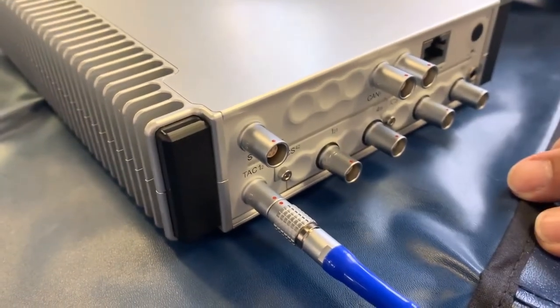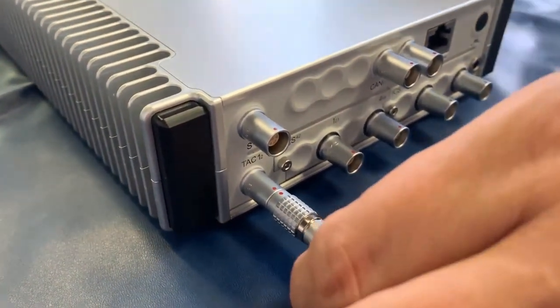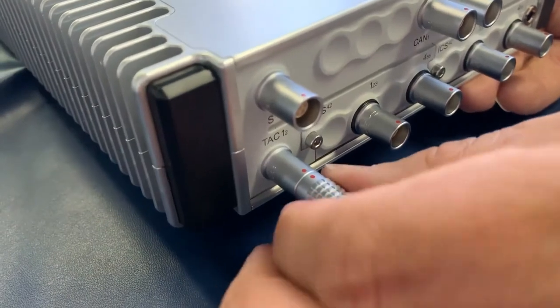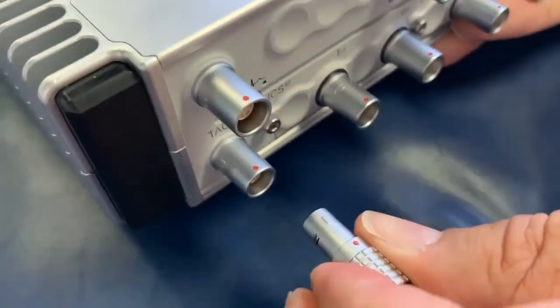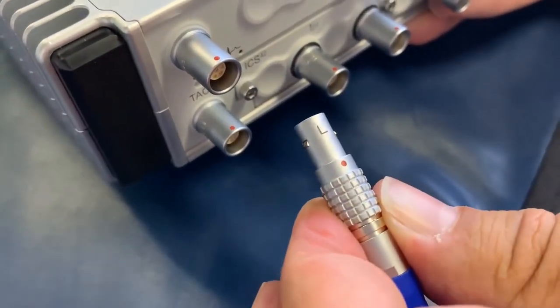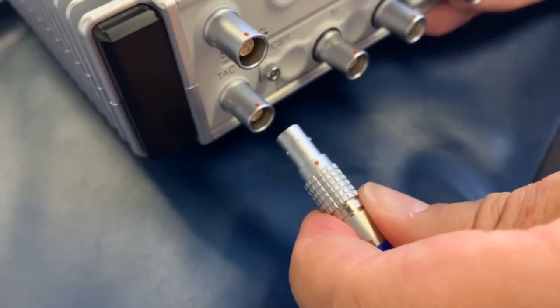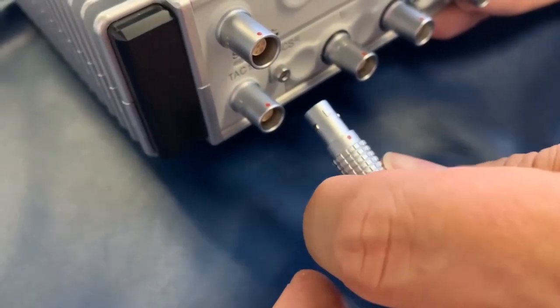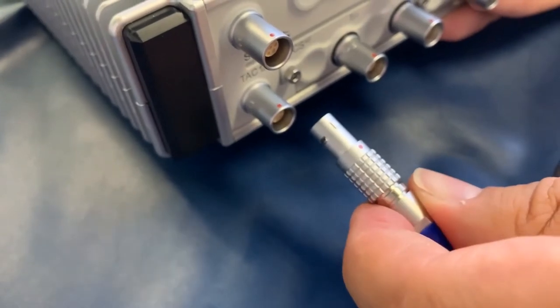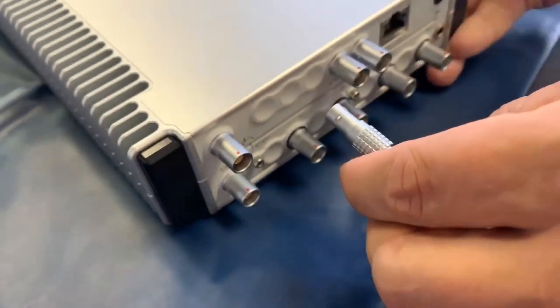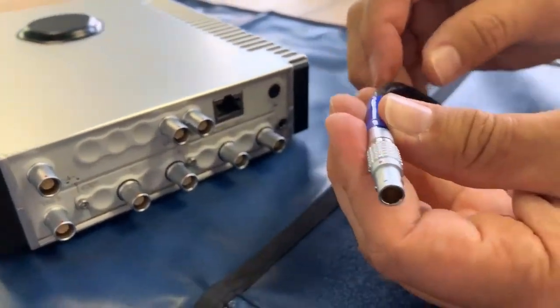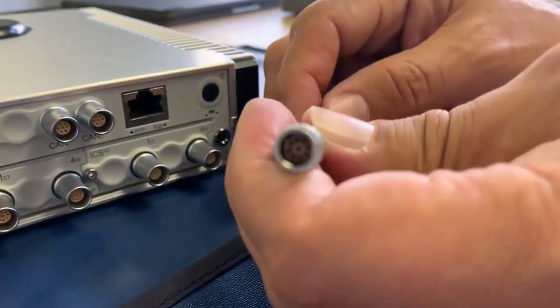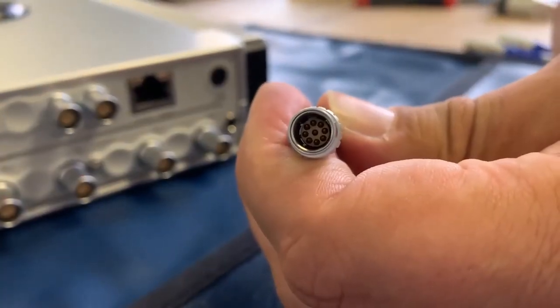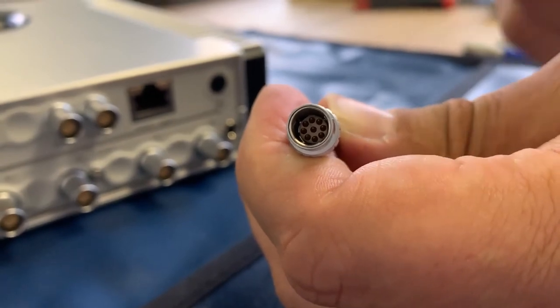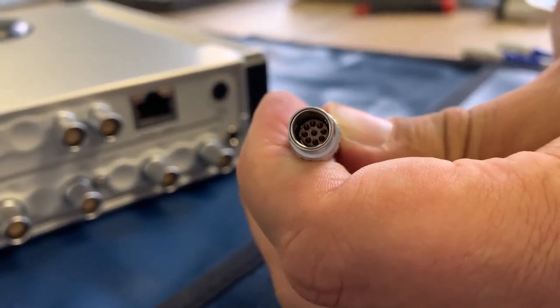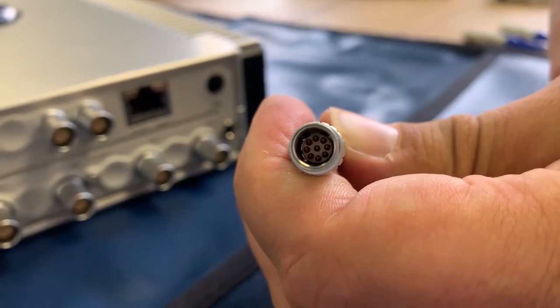Once you're done with your measurements, the proper way is to pull back on the knurled part again so that latch releases and the plug should easily come out. If you feel that it's not released, check that you're pulling on the right part of the connector. It should not be hard to disengage. Another thing to notice is that many of the Lemos on our system have the same size, and you want to make sure that you have the proper pins of the cable to the connector so that you don't force the pins and bend them.